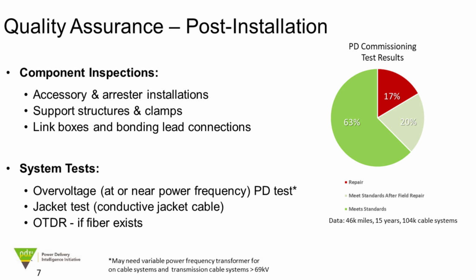Obviously, if you have conductive jackets, that jacket test is a really low-cost, simple way. Typically, that's only a high voltage or a transmission class opportunity. And if you have a transmission cable system, it's not very common with medium voltage, but if you have an optical fiber, you want to do a pre-test on that, an optical TDR, to make sure that that's properly installed.